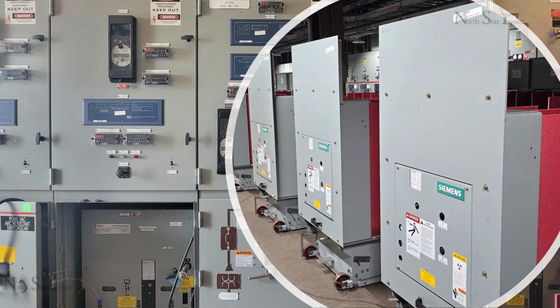Medium voltage breakers, typically used in larger industrial or utility settings, are similar in purpose but a little different in design. Instead of a built-in trip unit, they rely on external relays to send open and close commands. As a result, primary injection isn't applicable, but other tests remain vital. We perform Ductor and Megger testing the same as in low voltage breakers, but we also perform additional tests due to the added electrical components and higher voltages.